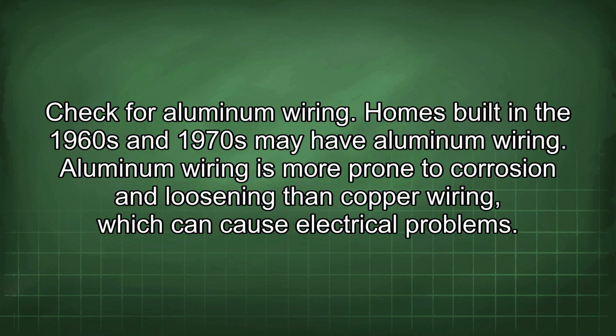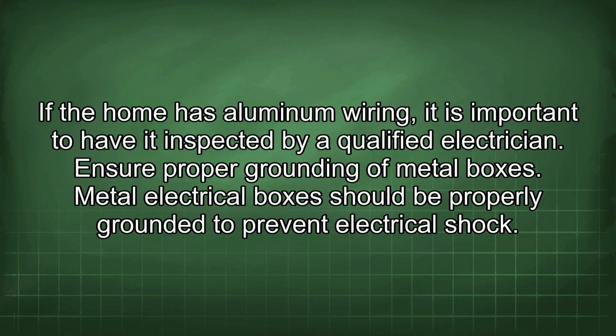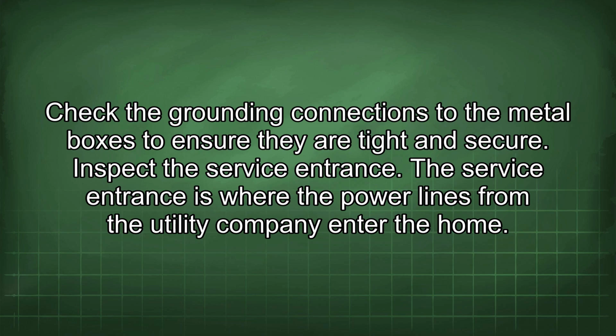Check for aluminum wiring. Homes built in the 1960s and 1970s may have aluminum wiring. Aluminum wiring is more prone to corrosion and loosening than copper wiring, which can cause electrical problems. If the home has aluminum wiring, it is important to have it inspected by a qualified electrician. Ensure proper grounding of metal boxes. Metal electrical boxes should be properly grounded to prevent electrical shock. Check the grounding connections to the metal boxes to ensure they are tight and secure.